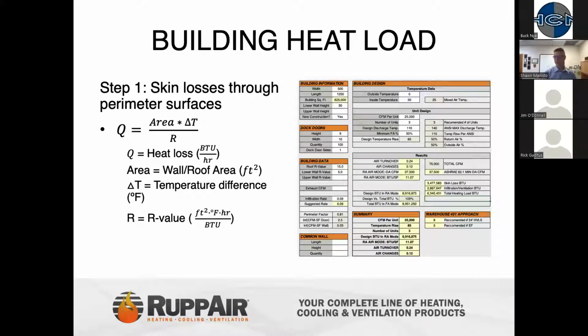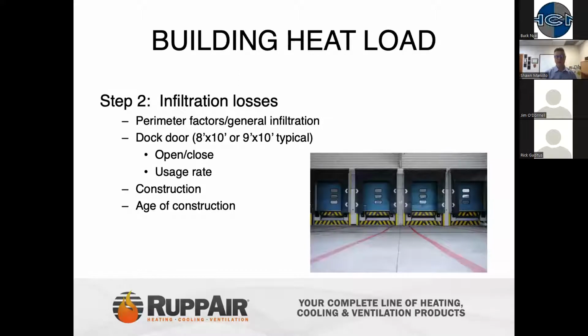In this case, this shows you a snapshot of the skin losses that are involved. And the big thing with the skin losses is most engineers can run this calculation and all your calcs are going to come up fairly close, plus or minus 5%. But the big part is going to be the infiltration factor. The infiltration factor is the key to understanding these buildings, how they live and breathe.